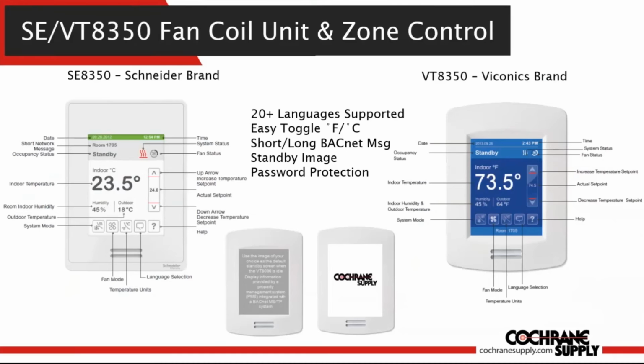The 8350 controller supports short and long BACnet messages. The short messages, here displayed as room 1705, support up to a 33-character message that can be anything from a welcome message, to which piece of equipment the room controller is connected to, like fan coil 237, for instance, or even an active value. Maybe you want to display the supply air temperature. This is also the area where alerts are displayed, like window open, dirty filter, or service alarm.